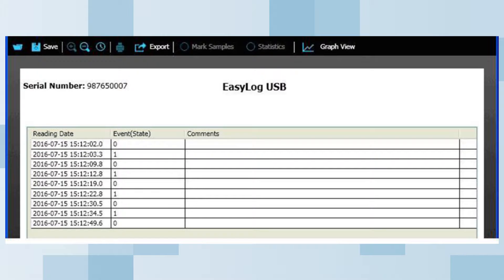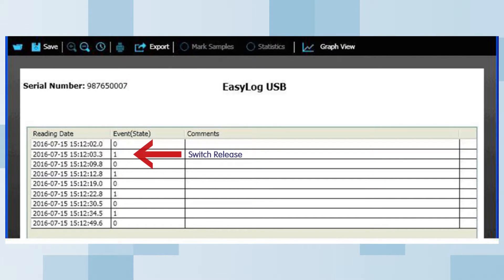The event column shows a low, zero, value for each switch press and a high, one, value when the switch is released. You may notice that an event is recorded at the end when the logger is connected to the PC. This may or may not be seen depending on the logger settings. To avoid recording an unintentional event when the logger is disconnected from the USB, following setup you should consider using the delayed start feature.